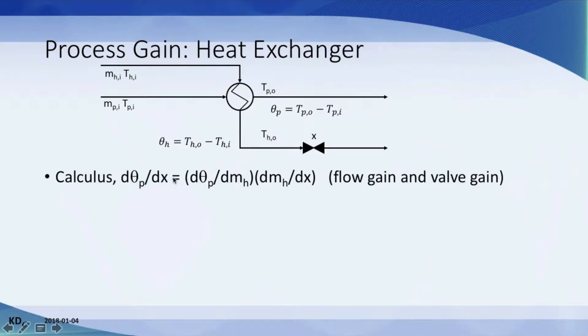The process gain is the change in process outlet temperature or temperature difference for a change in control valve position. With some calculus, we break this into two parts. The change in temperature difference for a change in oil flow rate is the flow gain. The change in oil flow rate for a change in valve position is the valve gain.